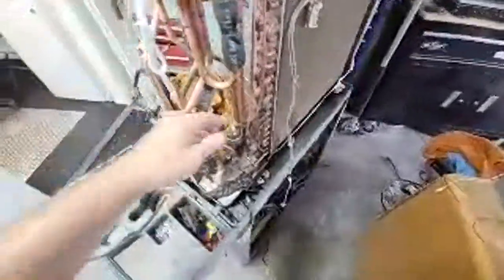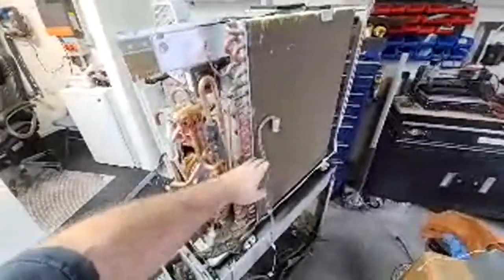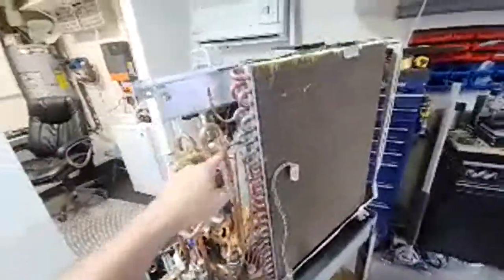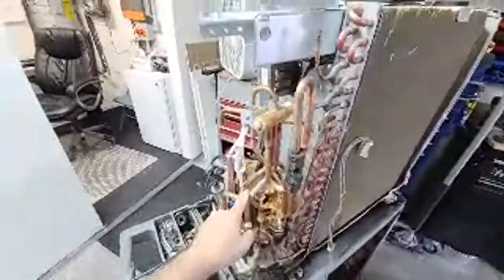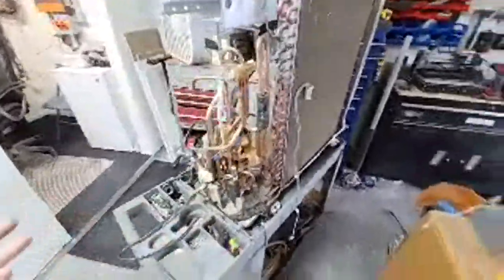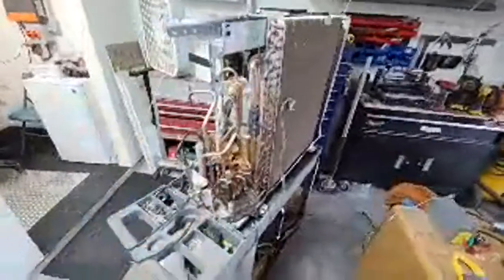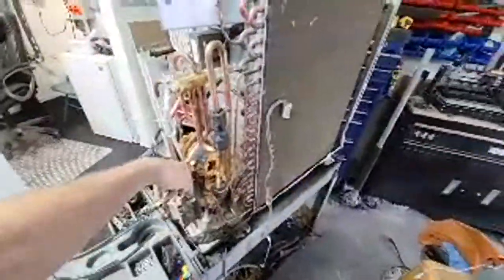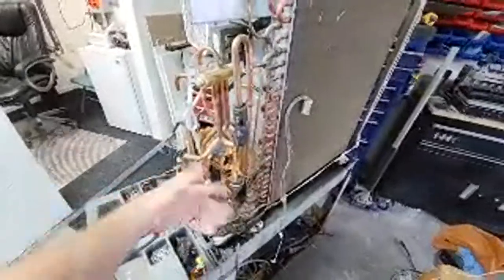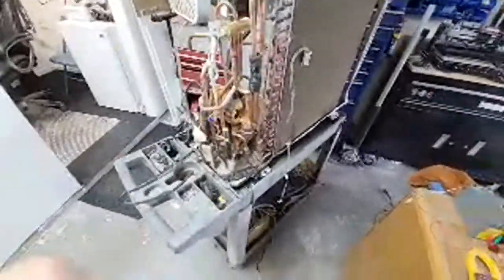And then I'm going to split this coil because this is a 1.5 ton unit, so it's like double almost what I need for coil. I'm going to take it and make it into 2 circuits. And you can see it is in 2 halves. I'm going to make the top half be an evaporator, I think. And it's going to have a second expansion valve go into it. And then this will be the suction, and I'll tee this suction with this suction so they both go to the compressor. And you've seen stuff with 2 evaporators. You just tie all the suctions together, and when you're not using one, you just drive the EXV to the closed position, and it's like a pump down solenoid at that point.